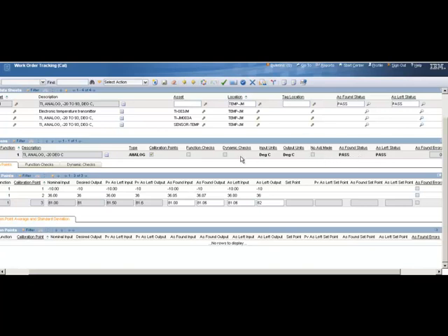And also, if all your functions pass, then your overall data sheet passes, as found, as left. So if I have 5 functions and 4 of them pass, 1 doesn't pass, well then my overall data sheet failed. It automatically calculates that out for you. So this is how a calibration technician enters a reading.